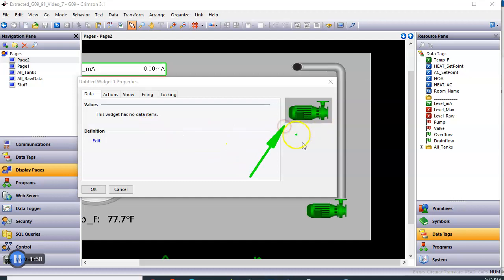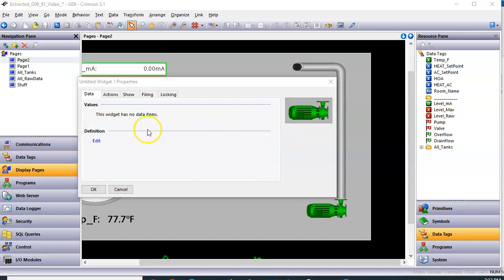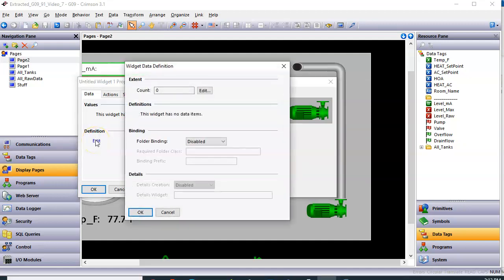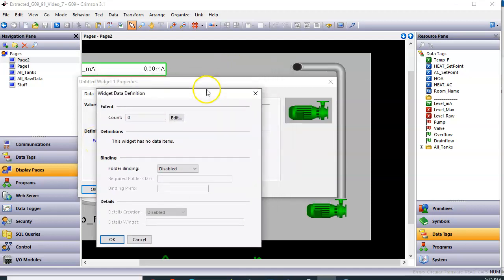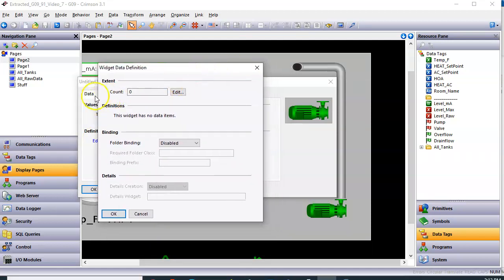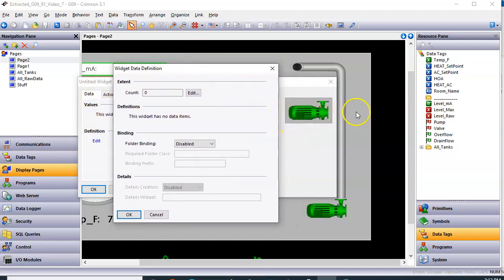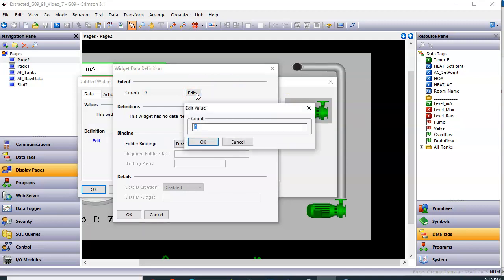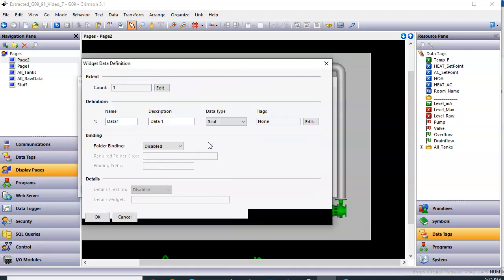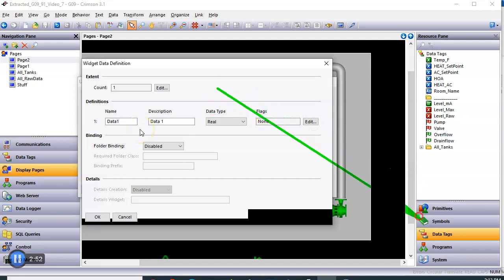Well, we know that everything in here is associated with one tag called pump. So what we're going to do is declare a widget tag that resides within this graphic. I'm going to click the button here for definition, click edit. And this brings up this pop-up. I'm going to click the edit button here for the count, put a number one in, and click OK. And now I get this section for definitions.